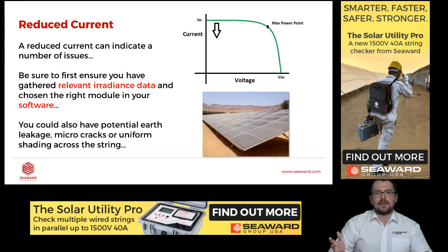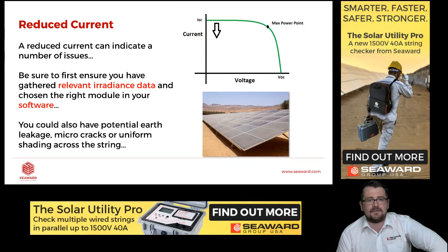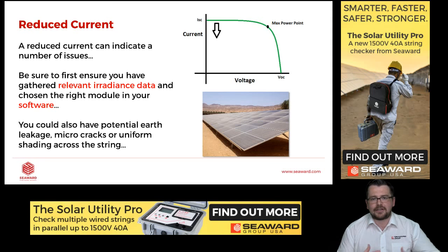So I mentioned that the different shapes of the IV curve can tell us different things about the PV array. And so I would like to cover some of the main points in this aspect and of the shape. And the first is a reduced current. So this can mean a lot of issues with the PV system, but what I would first check is that you're getting correct irradiance data. Okay, make sure that you're not getting higher or lower than what you should be getting.